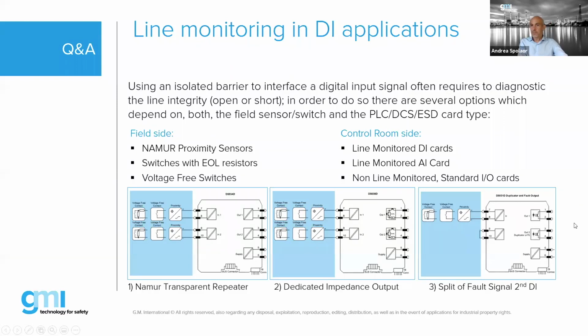The customer was looking for a digital input barrier for an instrument, like a level switch that provides 8 to 16 milliamp. In this case, for a line monitoring application, you can use an analog barrier for a digital application. That is also always possible. If you take a 4-20 milliamp barrier, you can transfer the information from a DI within the limit of the analog bearer, which is typically 0 to 22 milliamp.